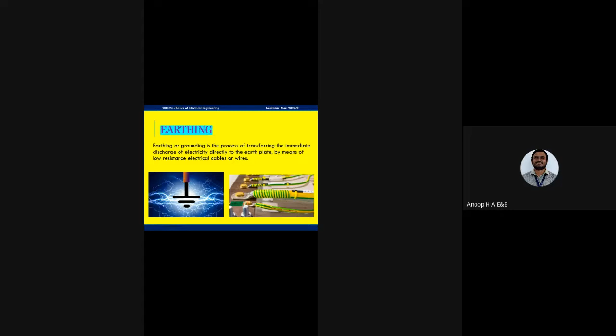Go to the type of earthing directly. Earthing is a safety measure. Which type of earthing is preferred in your house? Pipe earthing, sir. Explain pipe earthing: it is the most common type of earthing. Galvanized steel, a perforated pipe of certain length and diameter, is placed vertically in wet soil. Another type is plate earthing, where copper is buried in the ground at a depth not less than 3 meters.